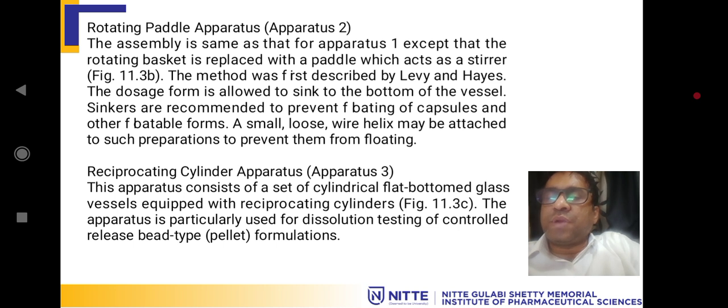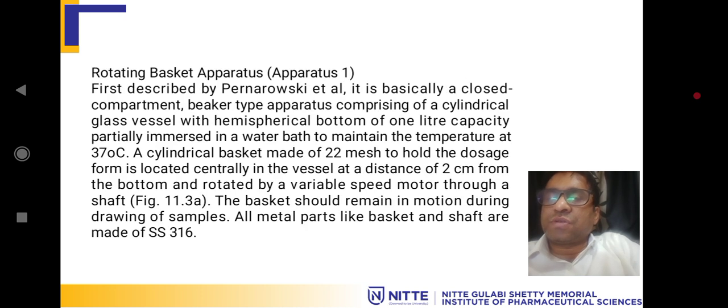Reciprocating cylinder apparatus. This apparatus consists of a set of cylindrical flat-bottom glass vessels equipped with reciprocating cylinders. The apparatus is particularly used for dissolution testing of controlled release bead type pellet formulations.